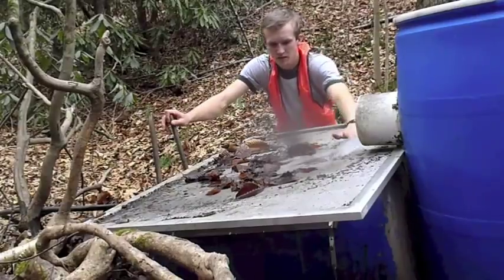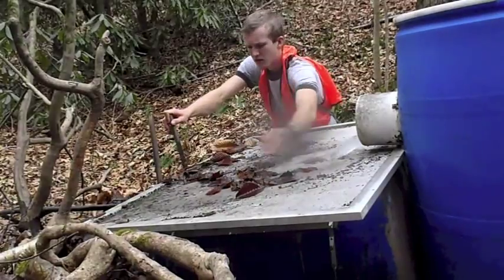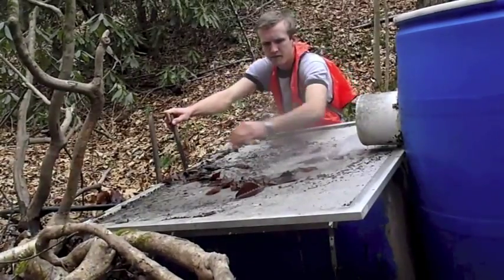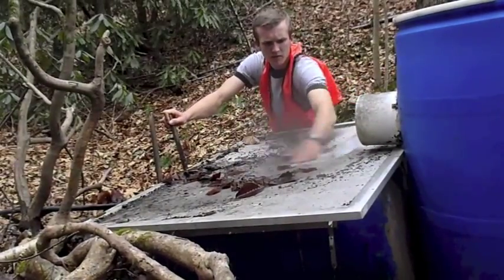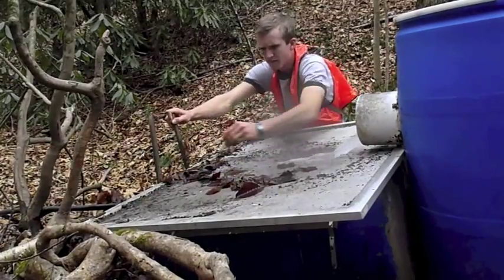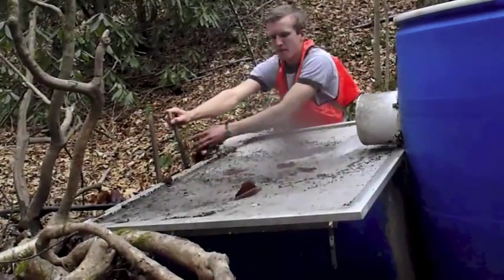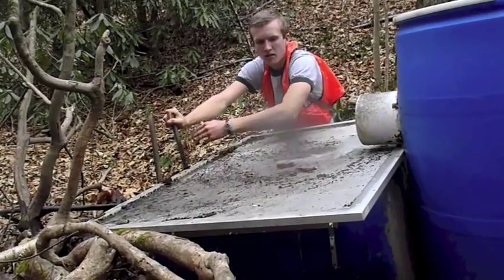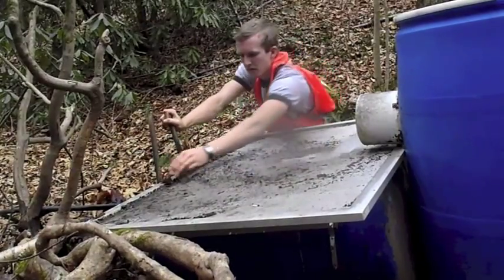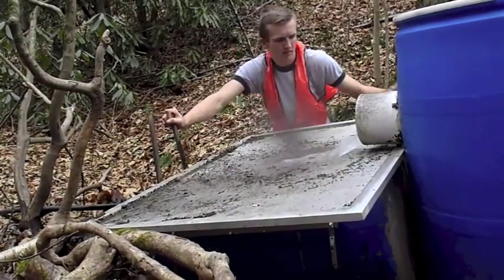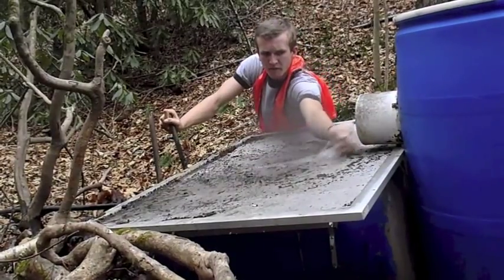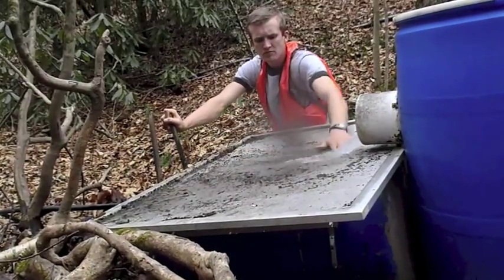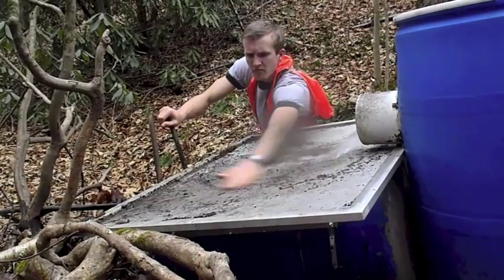The double silt filtration system at Molly's Branch Farm on the intake component is a fairly easy system to clean off, as you can see here with just a quick swipe of the hand. This component of the balance of system is essential towards the life of the turbine and also the penstock, because if any contamination buildup gets in the turbine or the penstock itself, it can damage it.